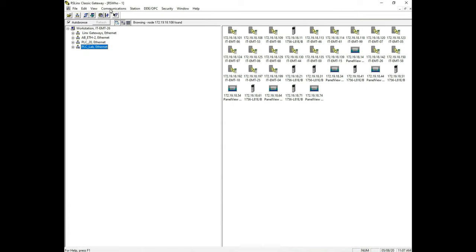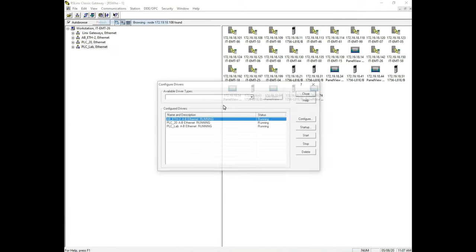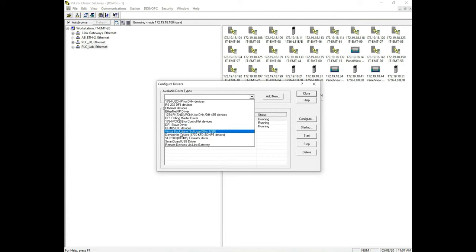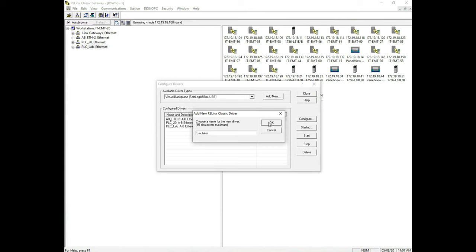Finally, we're going to set up a virtual communication because when we use our emulator, we need this virtual communication and we have to set it up just like we do a physical communication. So we go back to configure drivers once again. This time we're going to look for virtual back plane right here. See this? And we're going to hit add new. You'll see this whenever we set up our emulator, that our emulator network card is in slot zero. So I'm going to hit add new and then I'm going to name it. I'm just going to name this emulator so we know which one it is.